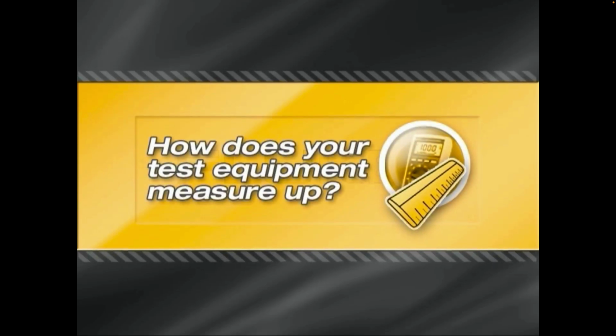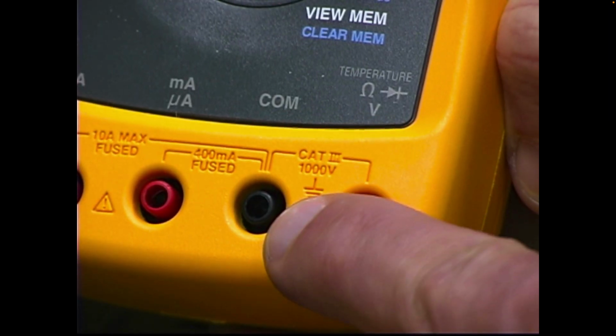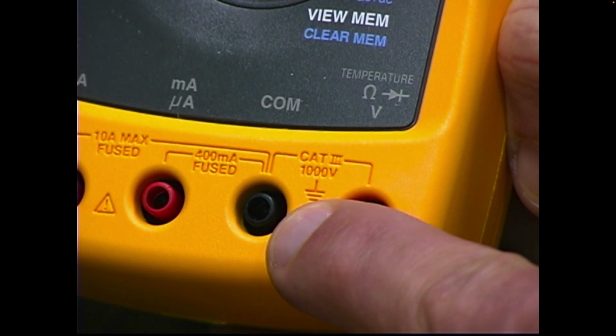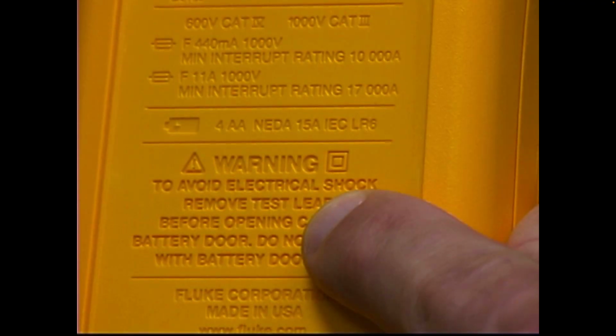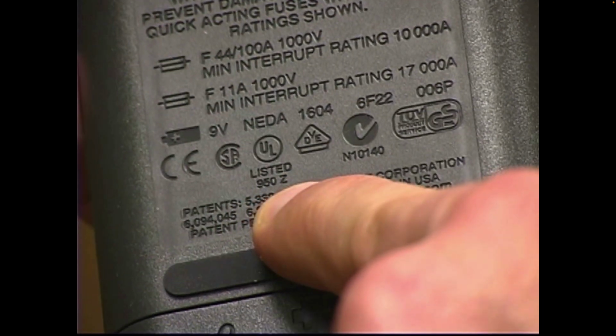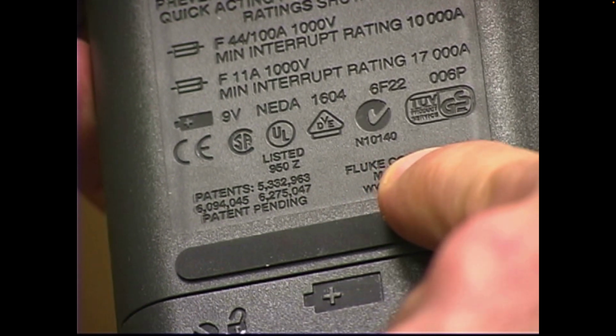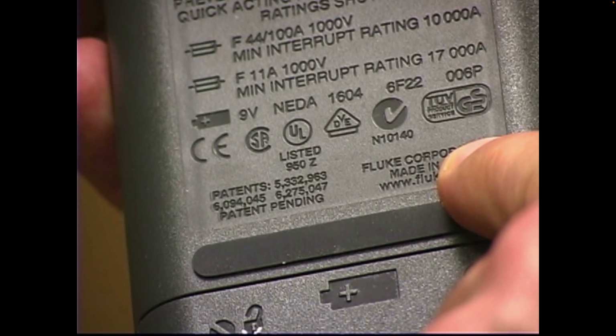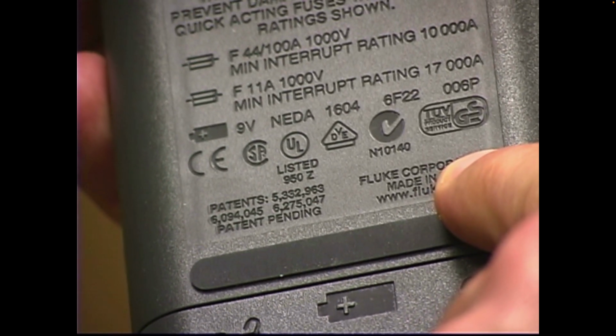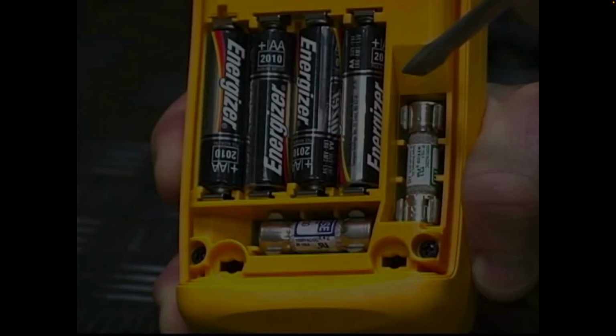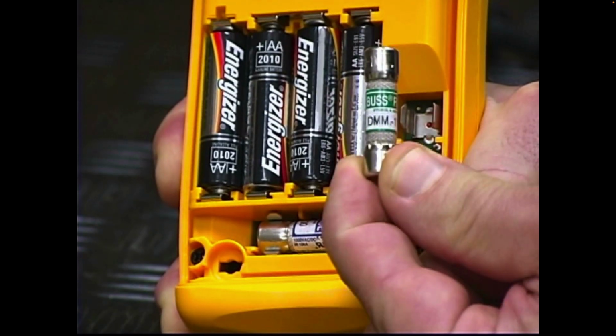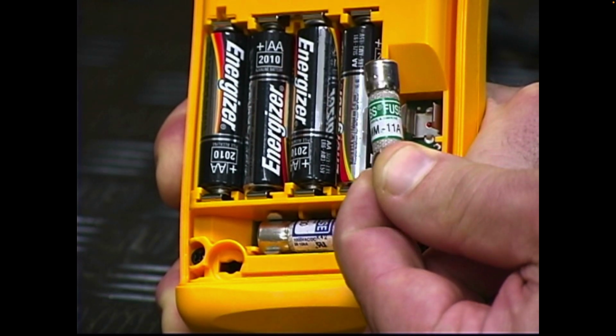How does your test equipment measure up? Here are tips for inspecting your own equipment. Look for the Cat3 or Cat4 rating on the front of your meter and testers, and a double insulated symbol on the back. Look for approval symbols from 2 or more independent testing agencies, such as UL, CSA, or TUV. Check the meter fuses for the correct amperage and voltage. Fuse voltage must equal or exceed the meter's voltage rating.